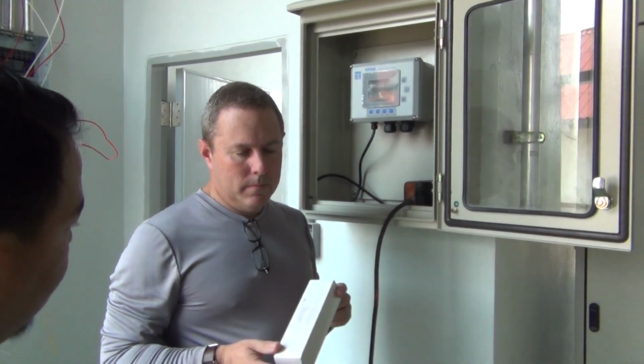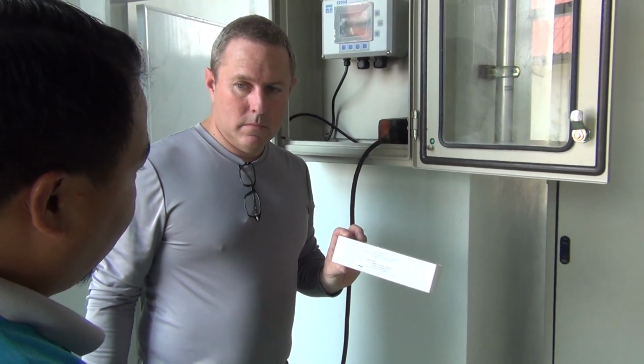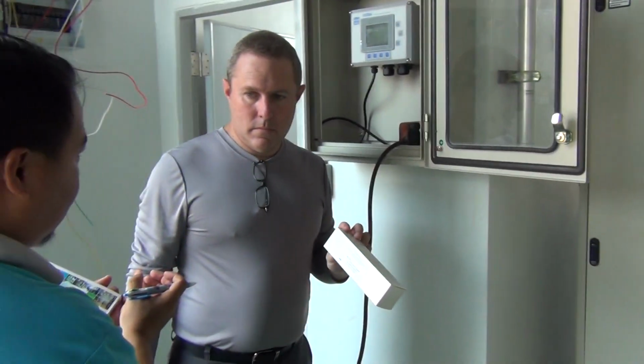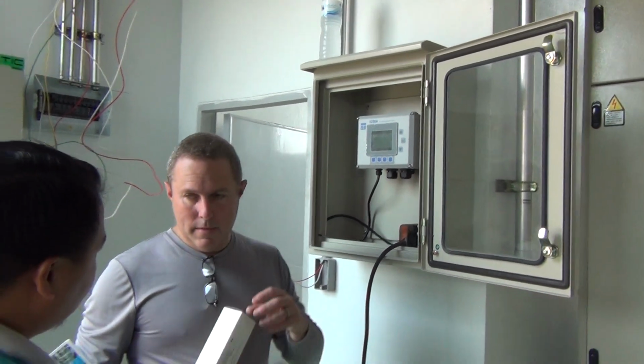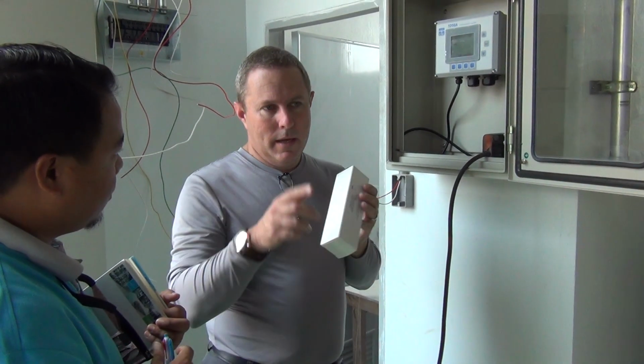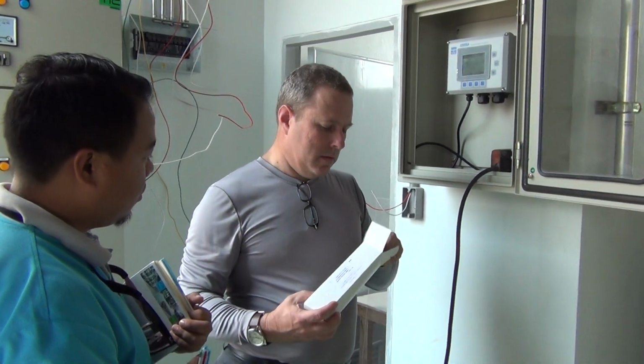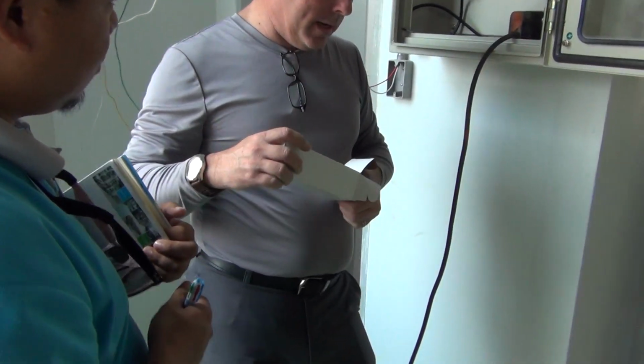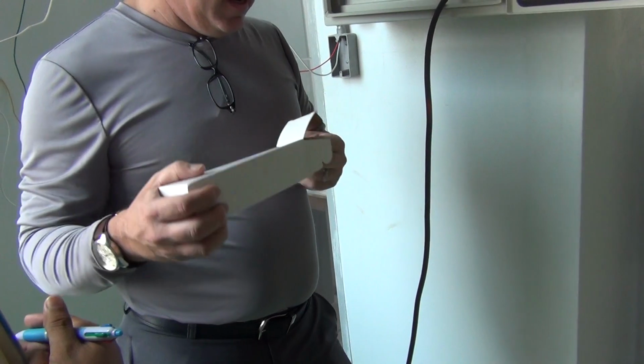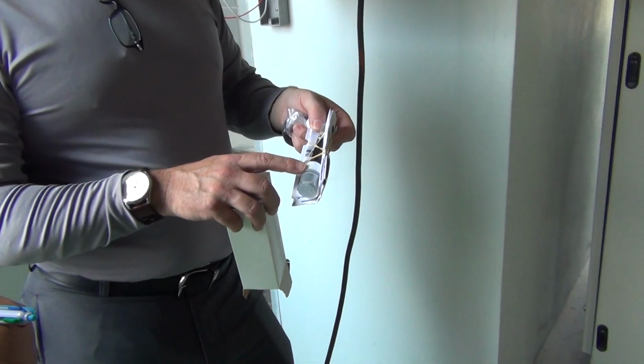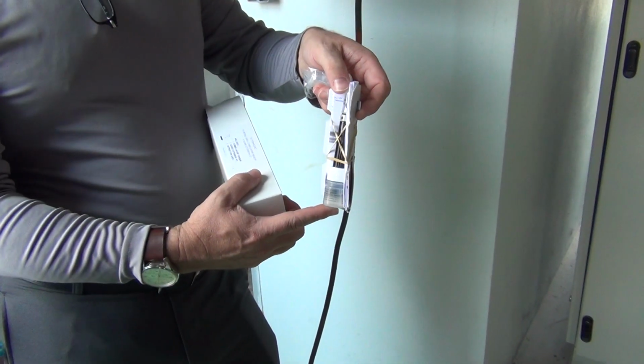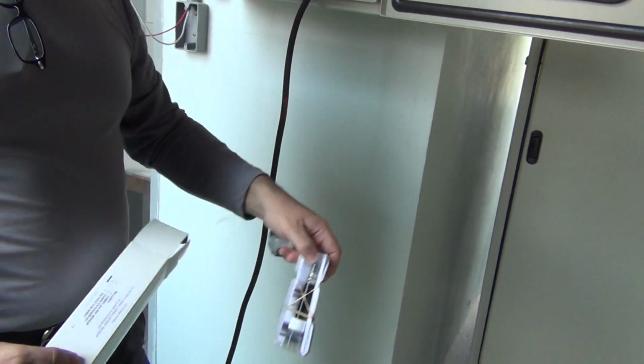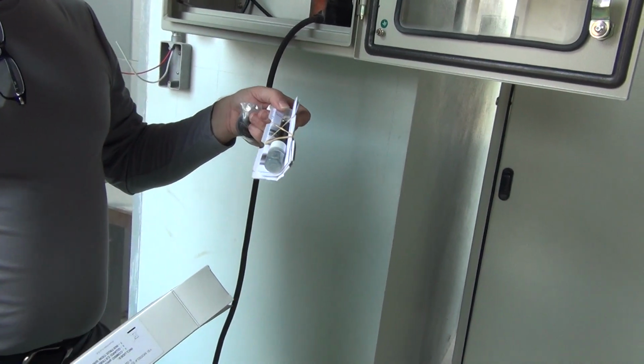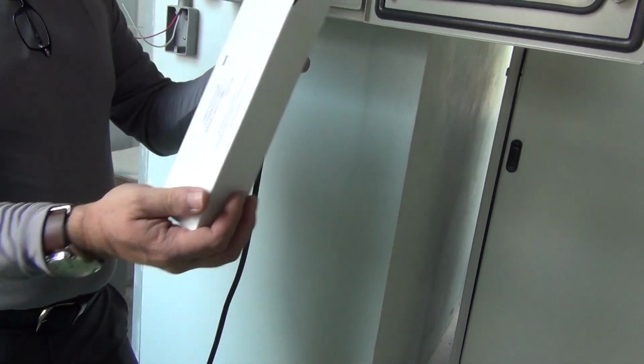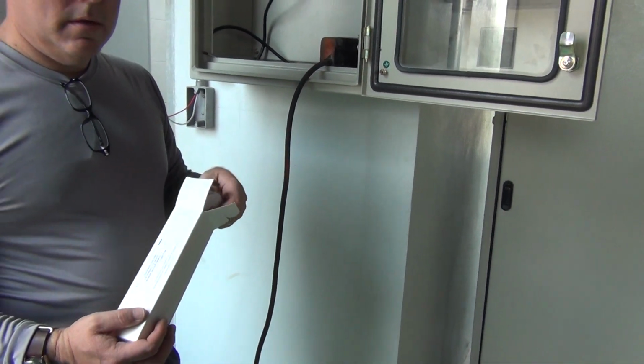While storing this probe, do we need to submerge it in the water or something like that? Yeah, this probe always has to be wet, either in the water, or if not in the water, it needs to be stored in electrolyte. This probe comes with a little ball and cap. What I would recommend is that in the dry season, we fill this with electrolyte and put it on just like that. Take the probe out of the cable and store it in the dry season. In the wet season, take this off, put it back into the cable, put it in, and you're good. Does this make sense now?